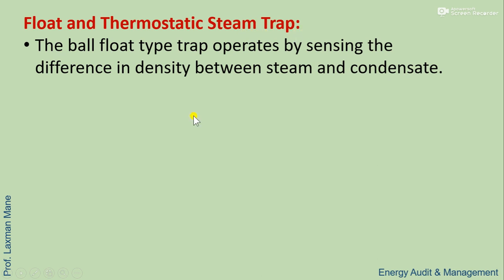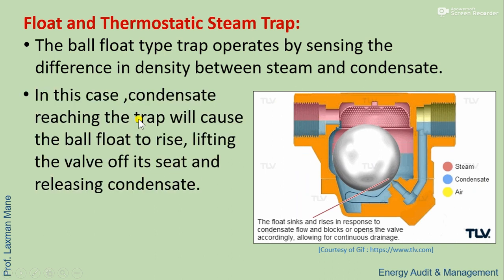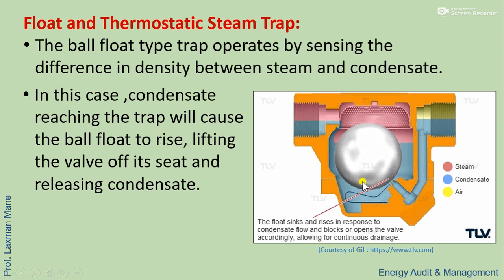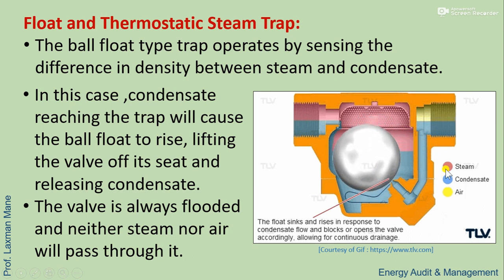The float and thermostatic steam trap: the ball float type operates by sensing the difference in density between steam and condensate. Condensate reaching the trap causes the ball float to rise, lifting the valve off its seat and releasing condensate. The valve is always flooded and neither steam nor air passes through — it allows only condensate. In this animation, red represents steam, blue represents condensate which is moving, and yellow represents air.